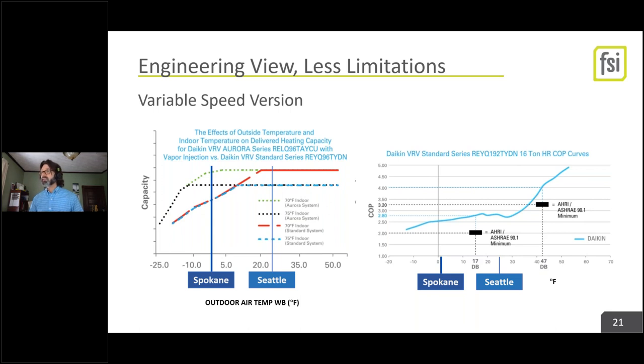And then on the right-hand side, it's COP, coefficient of performance versus temperature. So that's the other gospel, that your COP is horrible. You should just run an electric resistance heater at 45 degrees. And that is absolutely not true all the way down to the minimum these will operate at, negative 10. So you're still doing better than a COP of 2, even well into sub-zero temperatures. Correct. So that is a big deal.